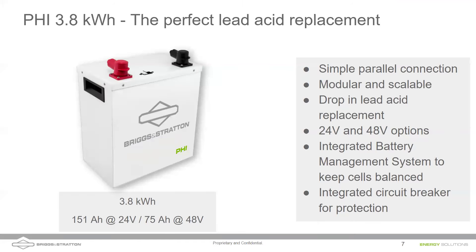Just to reiterate: we never wire our batteries in series like we would with lead acid batteries. One reason is that any current coming out of the first battery would have to pass through the BMS of the second battery, and the BMS units are limited in the amount of current they can handle. So if asked whether you can put two 24-volt batteries together to power a 48-volt system — the answer is no. Always wire in parallel.